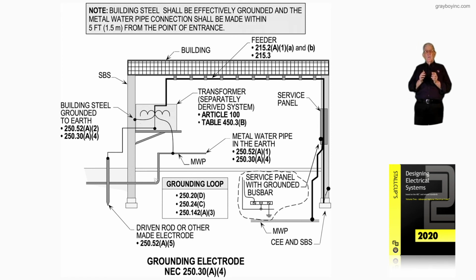And then notice in the grounding loop, you are suggested as users of the NEC, in viewing this illustration, to review 250.20(D) as in dog, 250.24(C) as in car, as well as 250.142(A)(3), as in apple 3. Now, reviewing these sections that you see in the illustration, you get a good handle on what is required for grounding the service equipment and then grounding the separately derived system on its secondary or at the first disconnecting means, as we have reviewed going through these illustrations that illustrate 250.30 in its entirety.